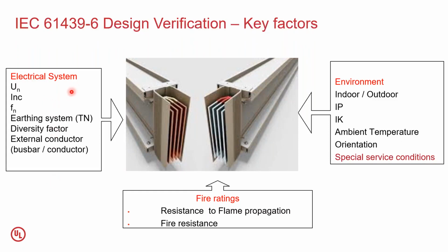In addition to the electrical system, you also need something related to the environment under which the busways operate. You need to understand whether the busways are to be used indoor or outdoor. Then you need to specify the required IP rating, the IK rating, and the ambient temperature requirement. Is whatever the standard says enough, or would you like some special ambient conditions, like 50 degrees for the Middle East? Most importantly, for busways the orientation also has to be specified: whether it is going to be used in a horizontal orientation, or also in a vertical orientation.